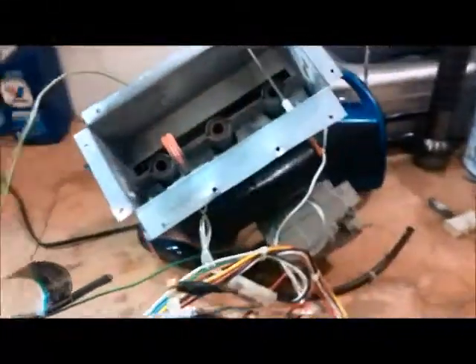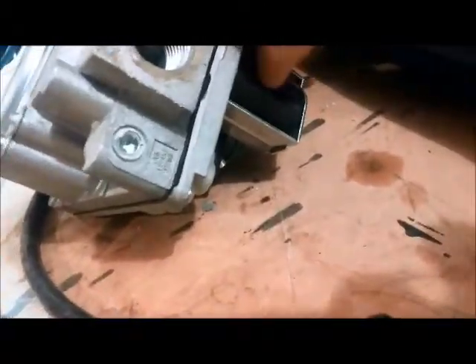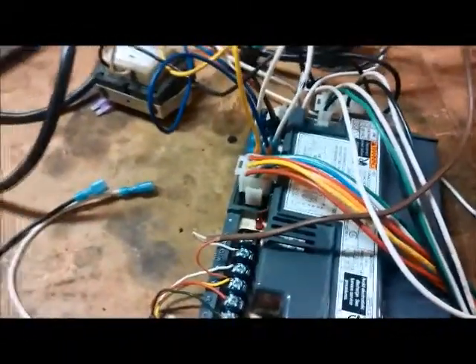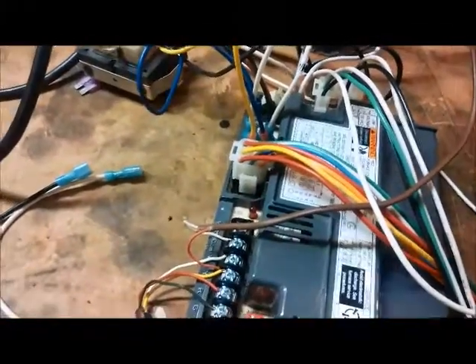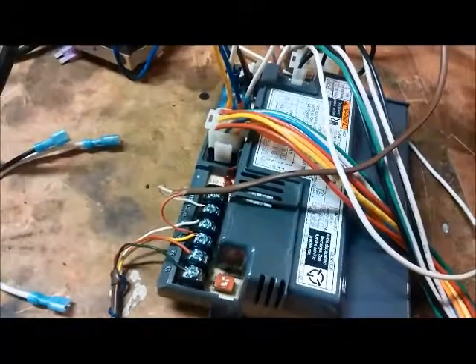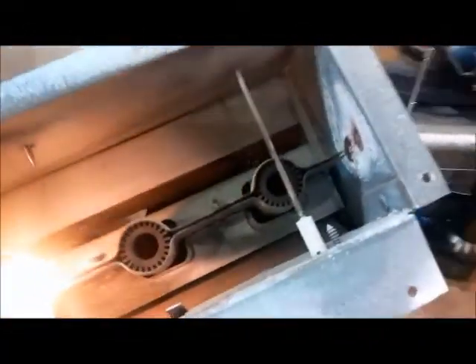Okay, it's a 3-4. So what's a 3-4? Ignition proving failure. So that's what happens when the gas valve does not open. Say the gas valve does not open. Could be a number of reasons. Wire could be off. Coil in the gas valve could be open, meaning burnt or disconnected. Maybe the board's not sending power to the igniter, which we know it is in this case because we saw it glow, but could have a bad flame sensor. Flame sensor could be just mucked up and dirty.